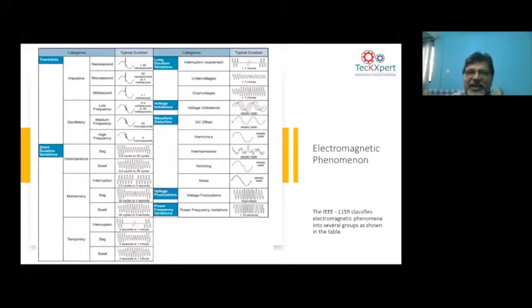That means if you look into that transient on the left side, it talks in terms of the duration: nanoseconds, microseconds, or milliseconds. That is, an impulse can remain in a network for a certain amount of duration, and it is also understood in terms of the magnitude. So how you characterize a transient is in terms of a magnitude and a duration, and again in terms of the rise time and the drooping time. So this is how a transient is classified.